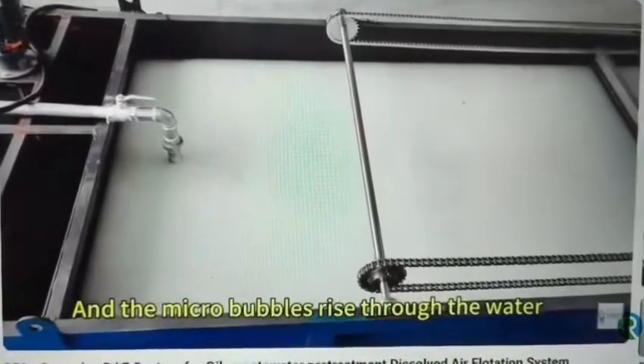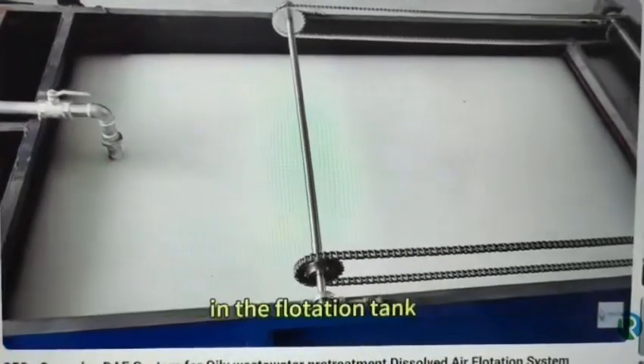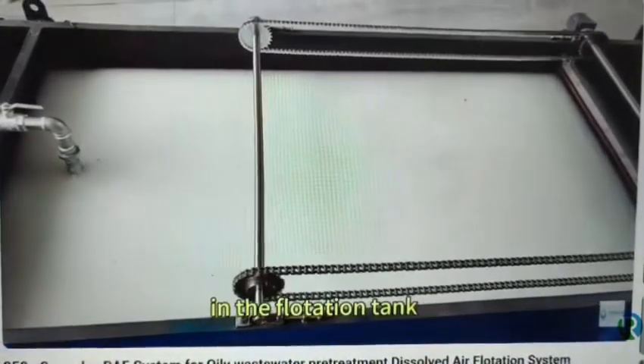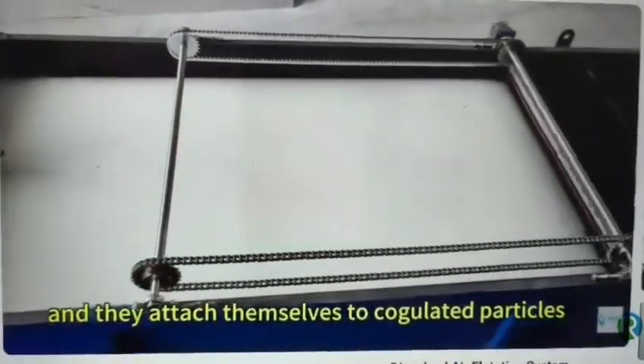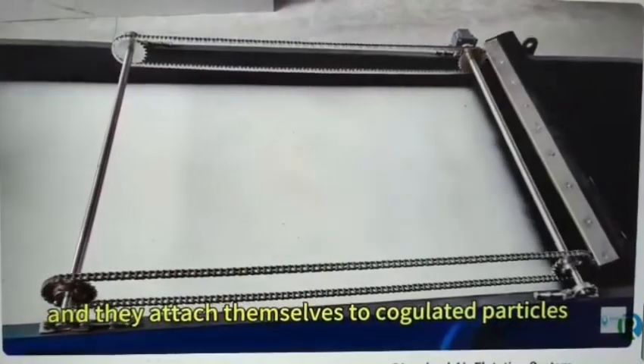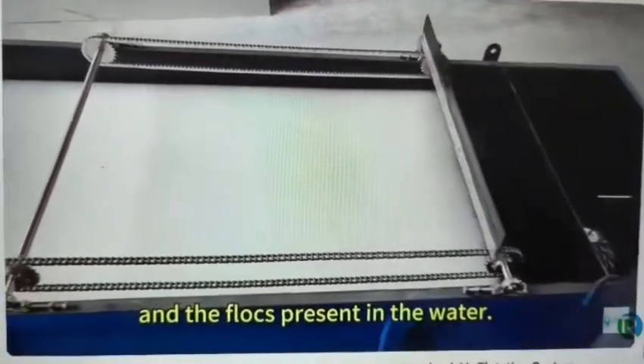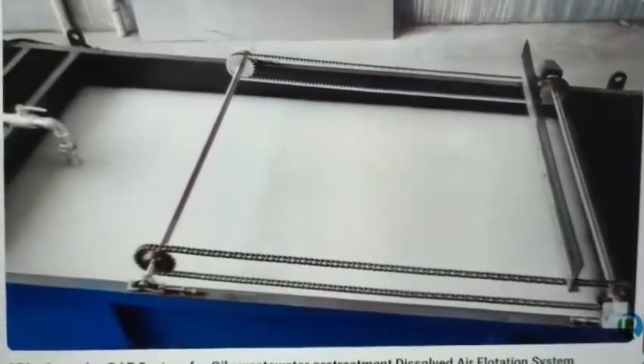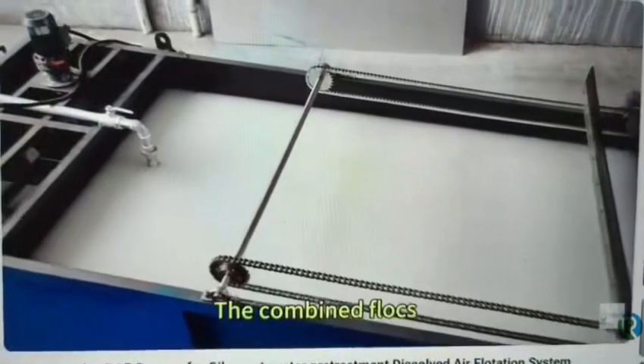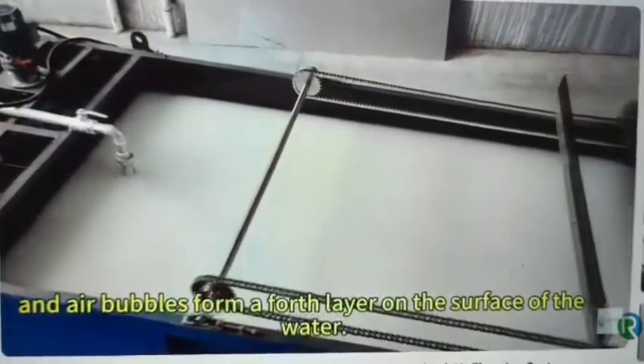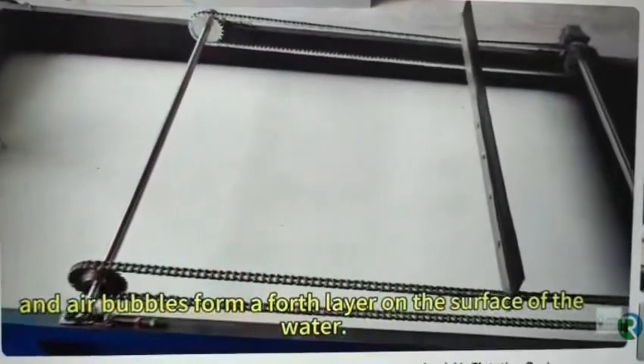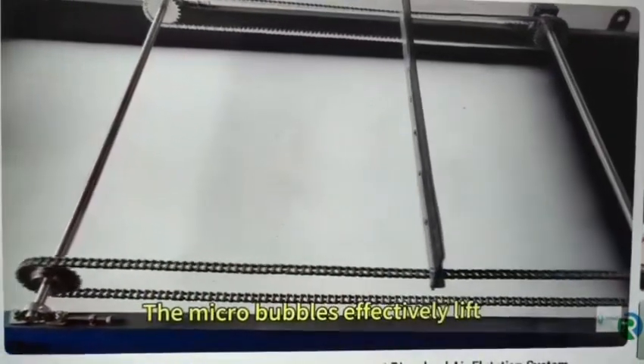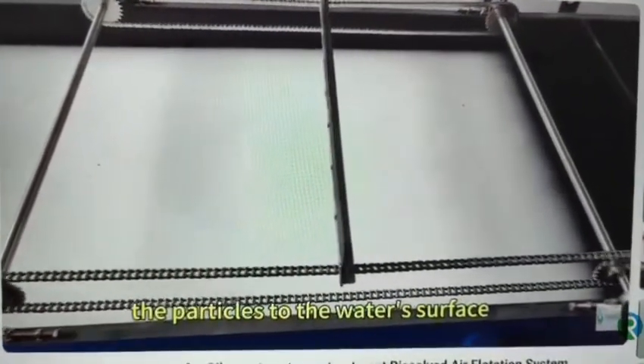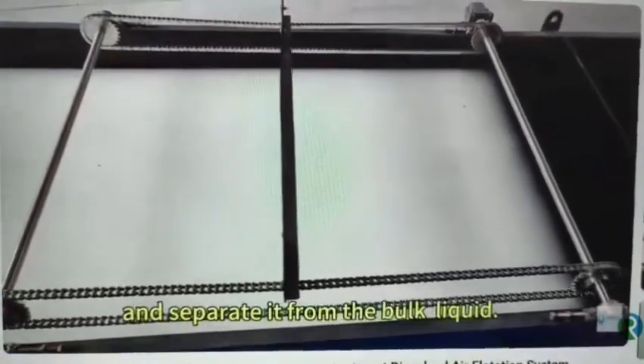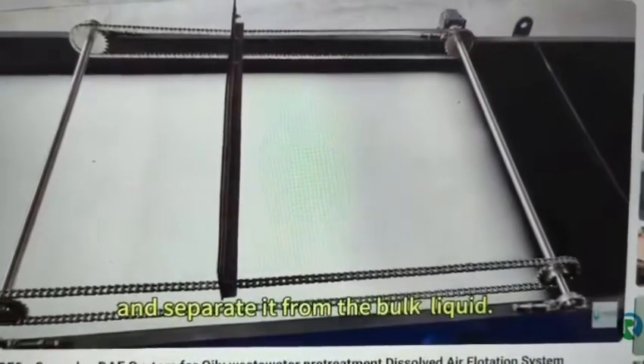And the microbubbles rise through the water in the flotation tank, and they attach themselves to coagulated particles and floc present in the water. The combined floc and air bubbles form a foam layer on the surface of the water. The microbubbles effectively lift the particles to the water surface and separate them from the liquid.